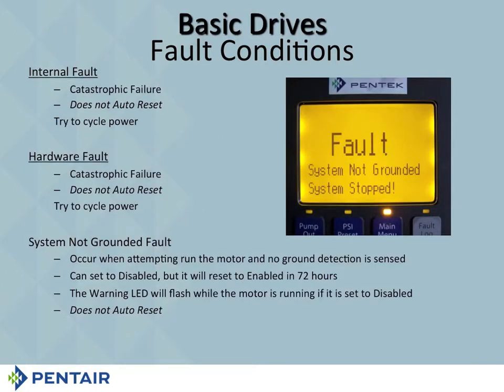Internal and hardware fault are the two you don't want to see, because those are catastrophic failures with the drive itself. Everything else we've talked about has been a system problem. And this is telling you, okay, fix the system problem. This one is saying, hey, this is a drive problem. Now, when your customer calls you and says the drive's not working, we don't have any water, ask them what the screen says. If it says internal or hardware, tell them to turn the power off to the drive.